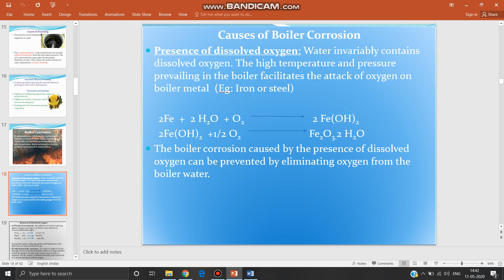But how to remove this dissolved oxygen? There are many treatments. One is chemical treatment and another one is mechanical deaeration. In chemical treatment, we need to add some oxygen scavengers or reducing agents like hydrazine, sodium sulfide and sodium sulfite. So, what happens in the presence of these chemicals? They will react with oxygen, and in the case of hydrazine, you will get water and nitrogen, and in the other two cases, sodium sulfide and sodium sulfite, you will get sodium sulfate. Out of these, hydrazine is the best reducing agent because there is no salt formation, only water and nitrogen. Nitrogen is anyway a gas, and water will add up to the water itself. So, that is one method.